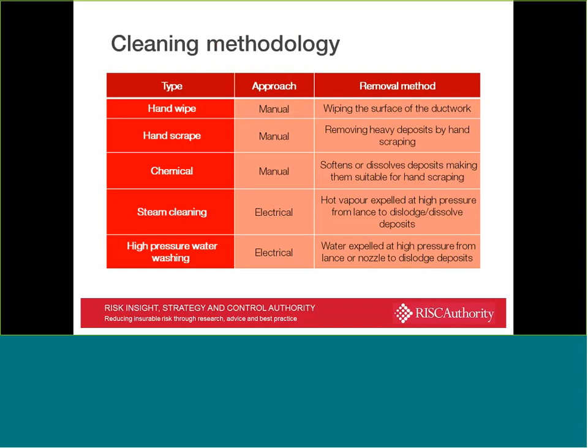There are several different cleaning methodologies. Again, you'll find this particular table in a number of different guidance documents, including our own and TR19. It's difficult to suggest whether some are better than others. At the end of the day, it's important that the system gets cleaned effectively, regardless of the approach that's taken. And hand cleaning, hand wiping and hand scraping can be just as effective as some of the other cleaning methods if it's done competently.